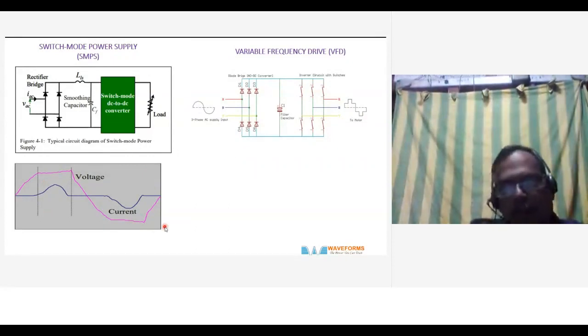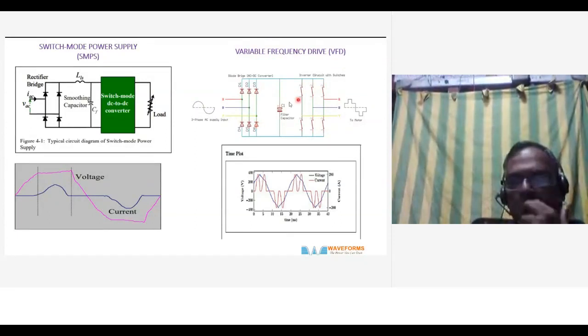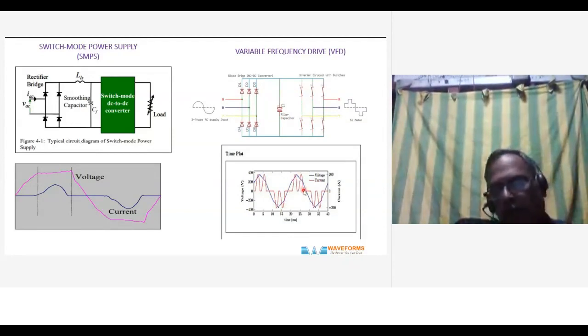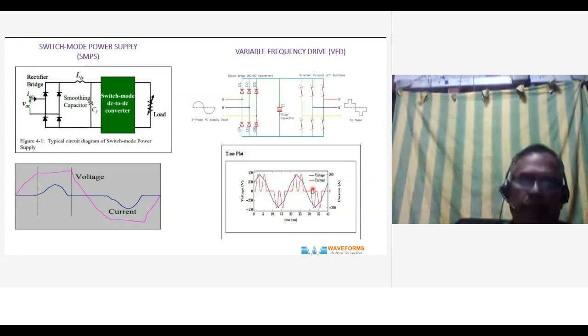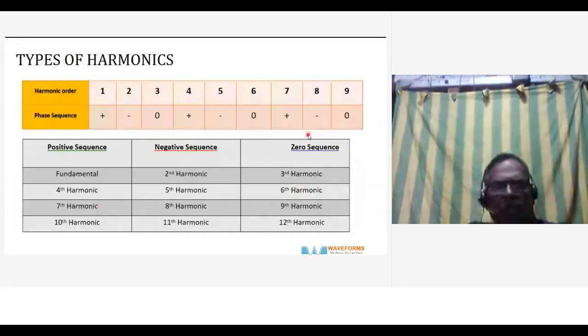So that's another thing. Then we also have the variable frequency drive. We call it VFD, we call it DSP, or whatever it is. We have the six diodes, okay, and the same thing, a filter capacitor. The input distortion, the voltage and current waveform, will be this type. The blue is the voltage waveform and the red is the current waveform. If you use a scope, you will find the waveform like this. On the power analyzer or in the scope, you'll find this type of input distortion in drives. Normally it will be to the extent of 40%, 60%, 70%, 80%. It depends on the quality of the drive, the design. So these are the two major loads that I projected.